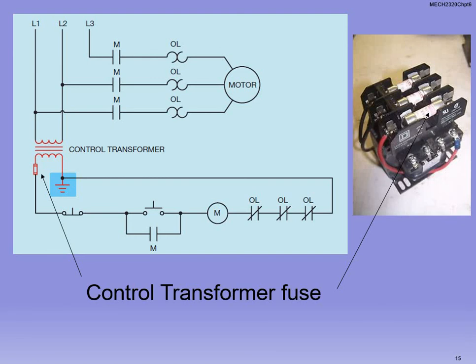Okay, we have a push button there. That's our stop button. Okay. Then we go over, we have a push button that's a start button, and it's in parallel with our motor contactor. Okay, so everything on the bottom of the schematic is your controls. So pushing that button manually starts the motor, right? We've already talked about manual switches. That motor, that circle with an M around it, okay, that's our motor coil, our contactor. That's not the official motor. The motor's at the top of the schematic here on the diagram. So that's our motor coil. So when we press the button, the motor coil energizes as long as the stop button is not pushed open and as long as we're getting power to the transformer.